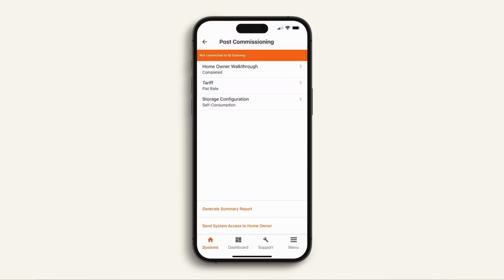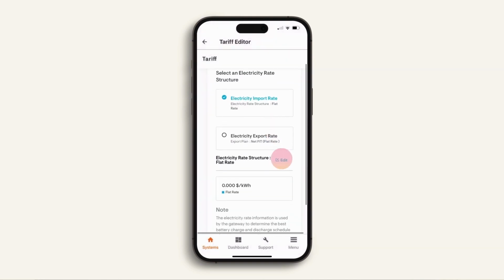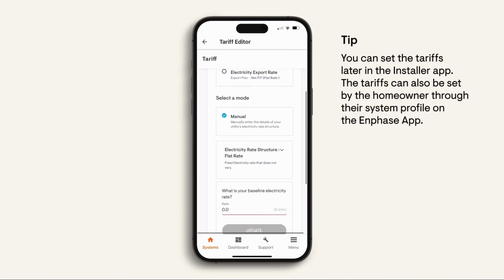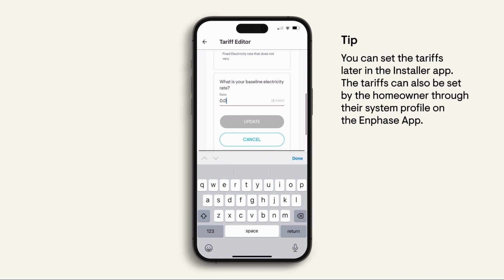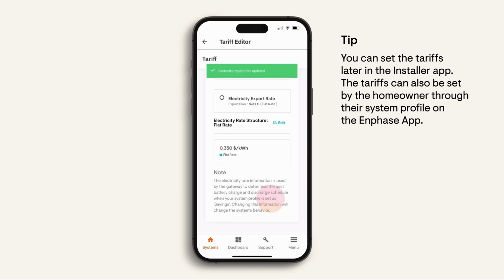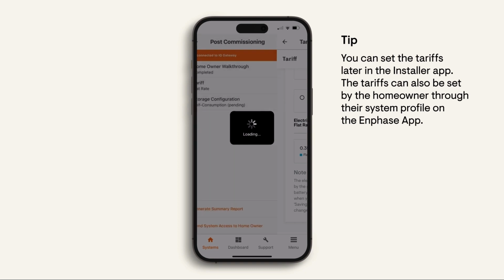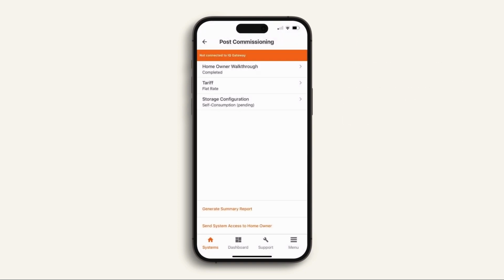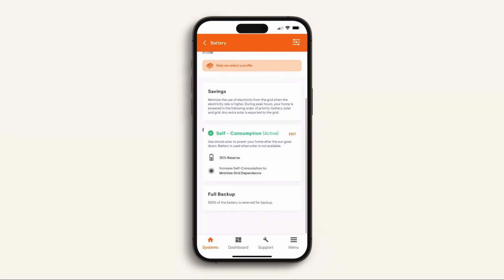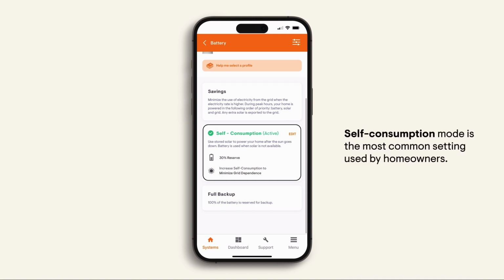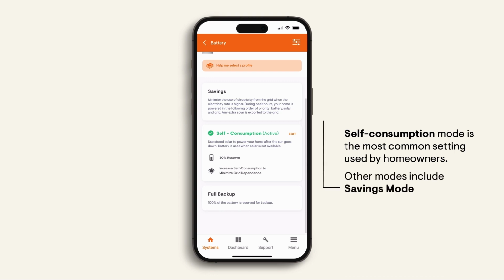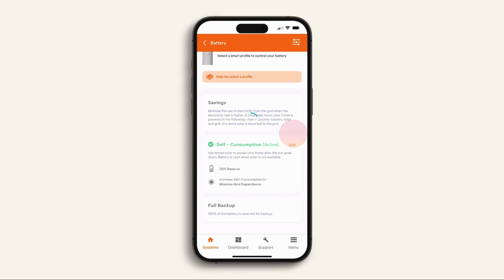Click back to post-commissioning. To set the tariff amounts, you will need a copy of the customer's power bill for the correct information. You can also set storage configuration, which will determine how the battery energy is used. Self-consumption mode will prioritise the battery and solar, minimising the amount of electricity being purchased from the grid. And you can also set the backup reserve capacity to guarantee there will always be the battery energy available when the system is operating in off-grid mode.